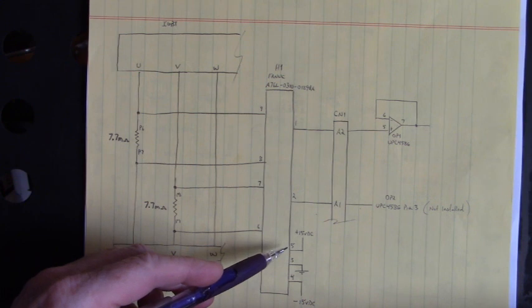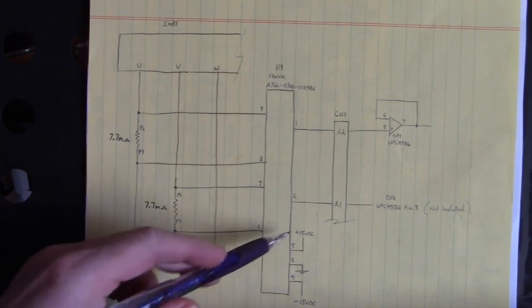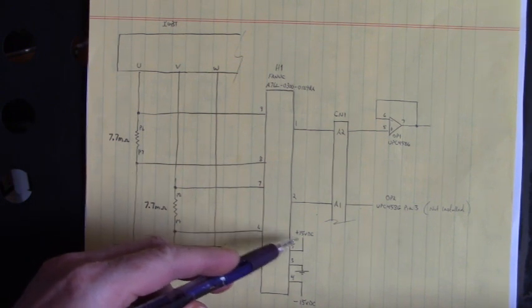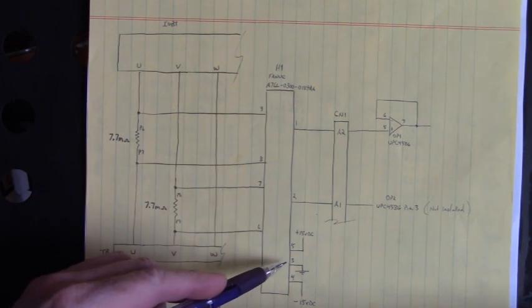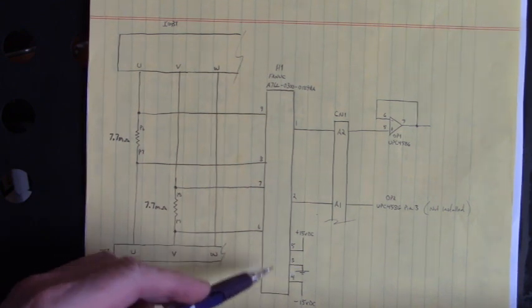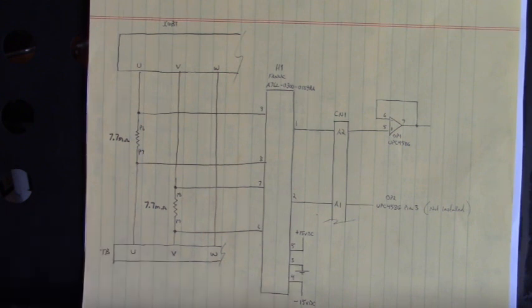On pin 5, terminal 5, 3 and 4 are the supply inputs to power up this module. Pin 5 is plus 15 volts DC in. Pin 3 is ground. And pin 4 is minus 15 volts DC. Let's go look at the hookups to perform the test.